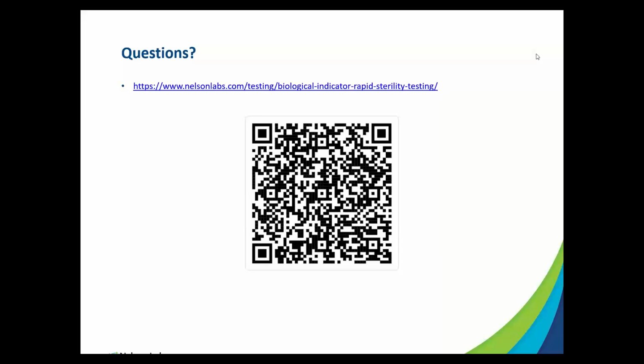So this might depend if you're looking at a validation. So this question is for a validation approach. It may depend on the number of cycles that you're running, because certainly if you have multiple cycles going through this process, there can be significant time savings there, as that would continue to add up for every cycle that's being run. So it really depends on the specific situation, but each individual test would still have that 2-day, that 48-hour minimum incubation for the RapidCert.